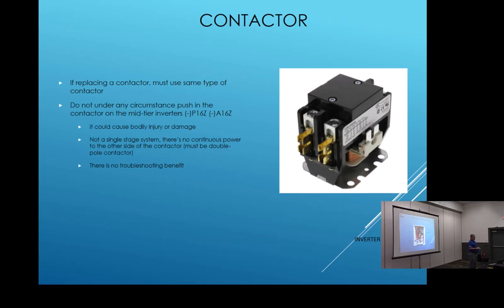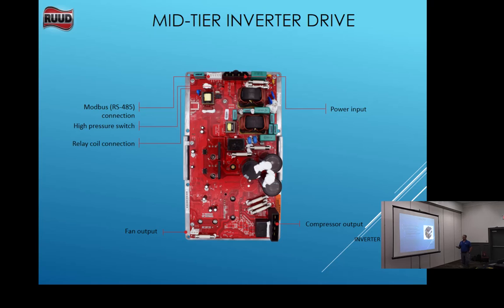Don't push the contactor in. This is our inverter board. This is our fan output. This is our brushless DC fan motor. I had one the other day that I had to send back, first one that they had seen, but the brushless DC fan motor shorted out and burnt the board right here. Okay, so they hadn't seen it either, so we sent it back. I haven't heard anything back from them, but it did happen.